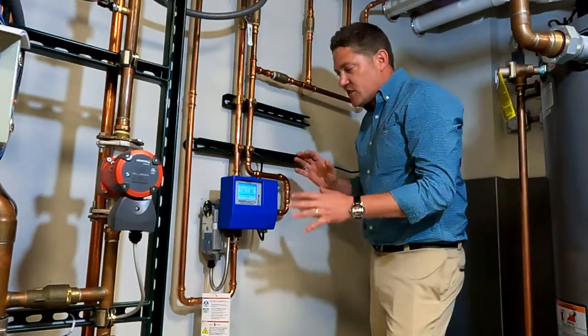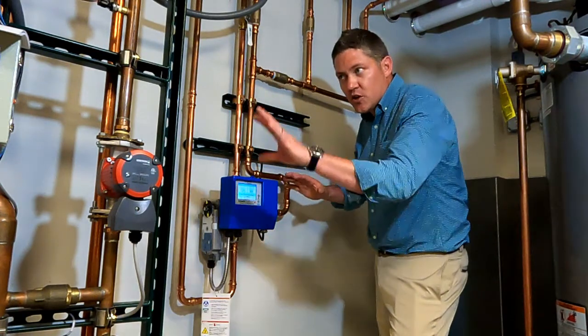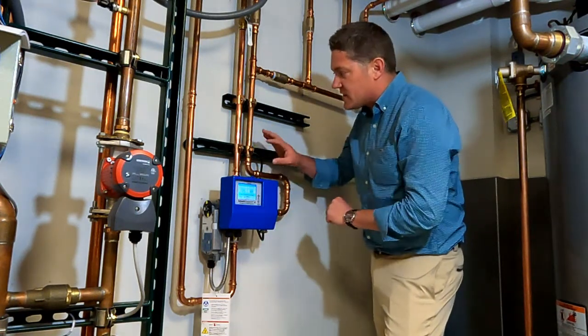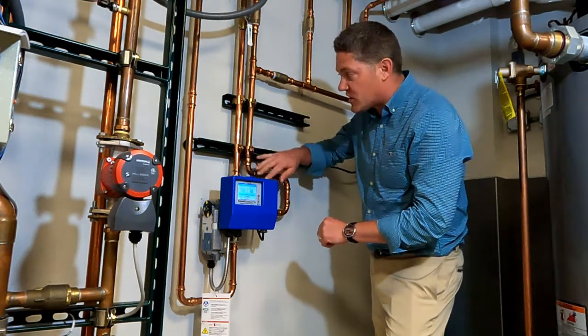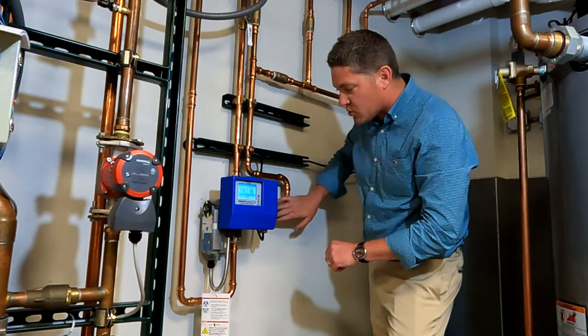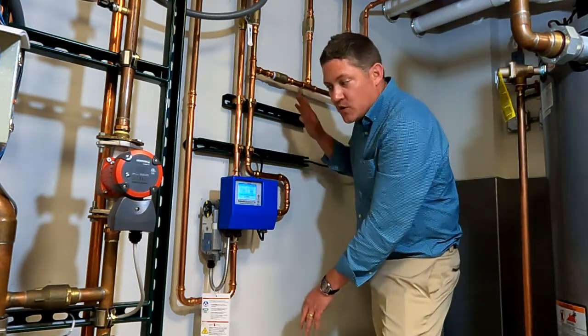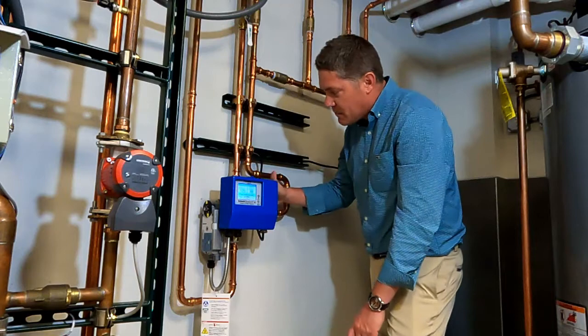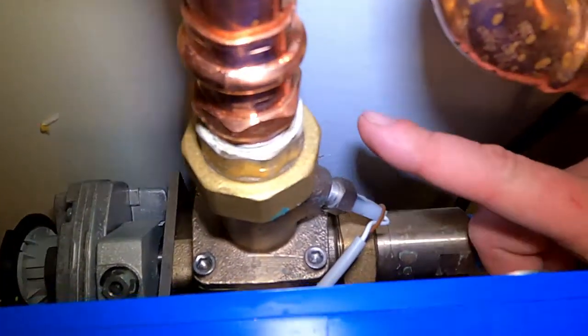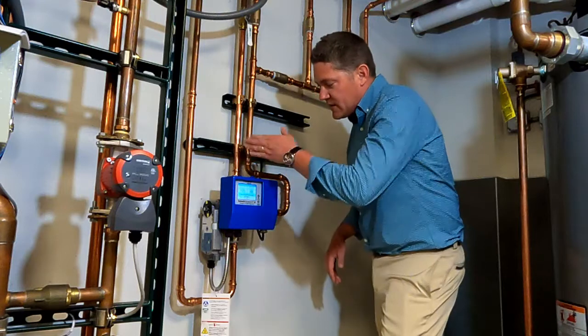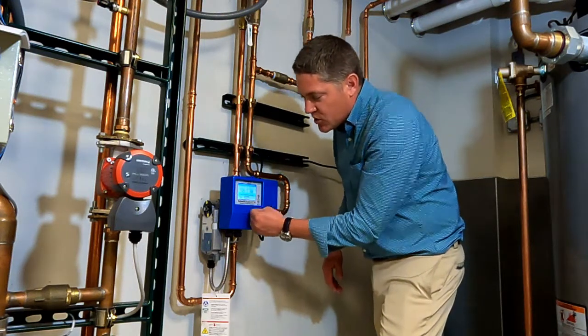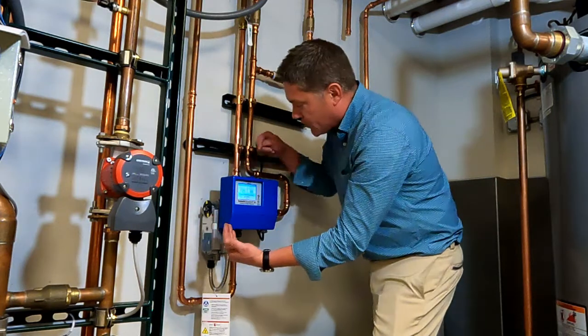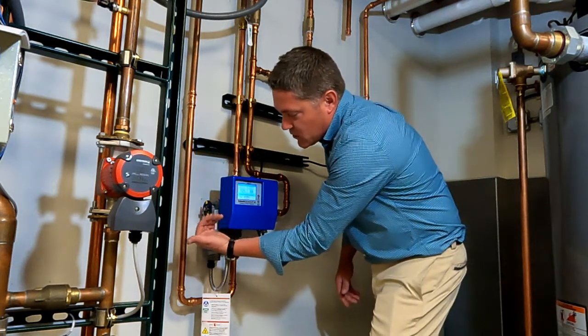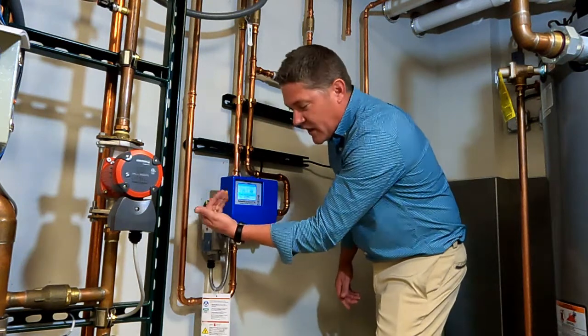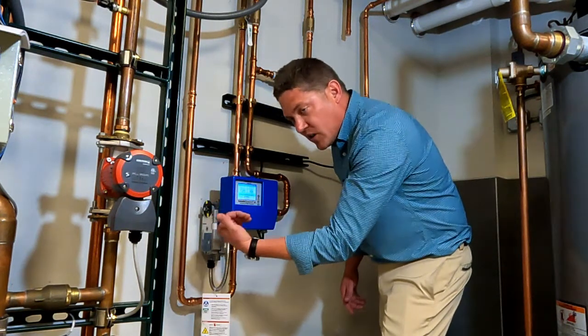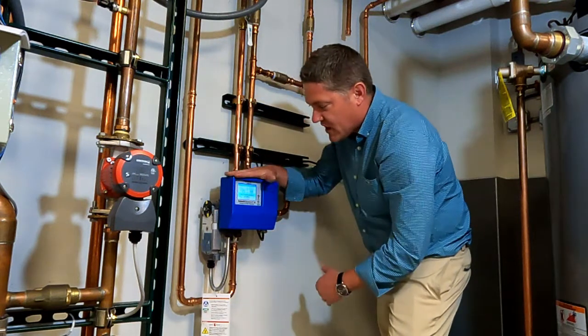So here we have the Intellistation Jr. The thing is very similar to the Intellistation Sr, only instead of having a temperature and pressure sensor on your mixed outlet, your cold inlet, your hot inlet, and your return, it only has one sensor. A temperature sensor on the mixed outlet in the back. The whole thing's controlled through that. So that temperature sensor sends a reading to the controller. The controller moves your actuator on the 3-port ball valve, and that actuator is moving the stem on that 3-port ball valve, letting in a little less cold, or a little bit more cold, or a little less hot, a little more hot, to hit your desired set point.